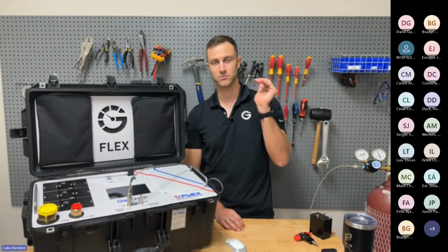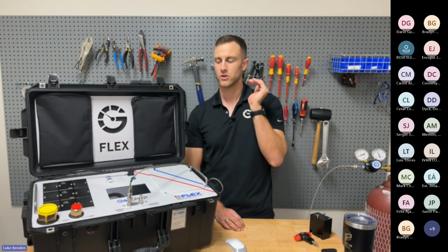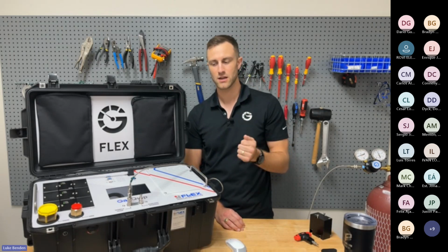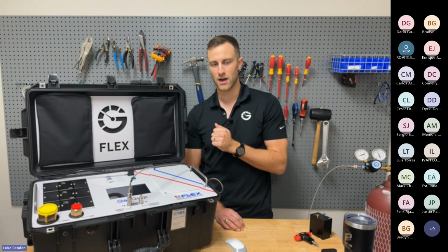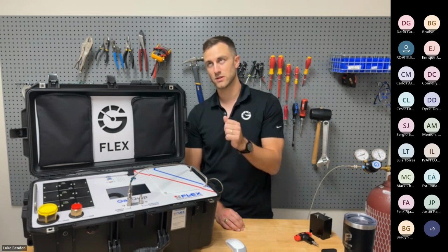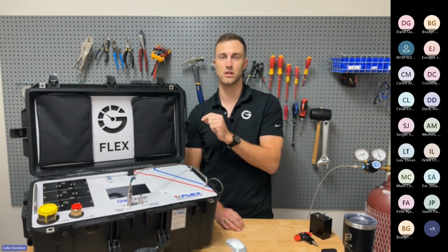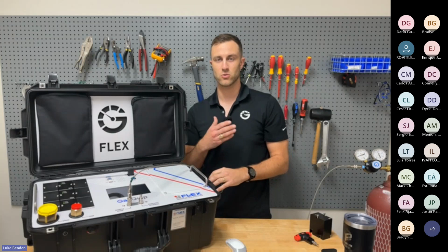Past that, if you're getting high readings on your H2O sensor, you can run that system dry out that we talked about earlier. You can run a leak check to make sure you're not leaking. If you have SF6 readouts that you think are lower than expected, you can also run those two functions.